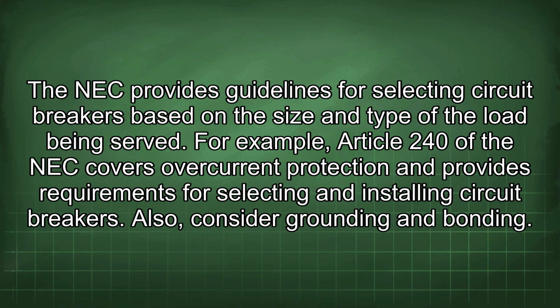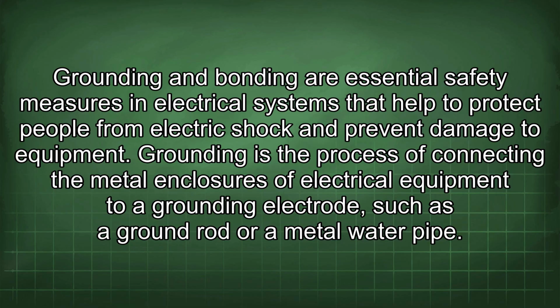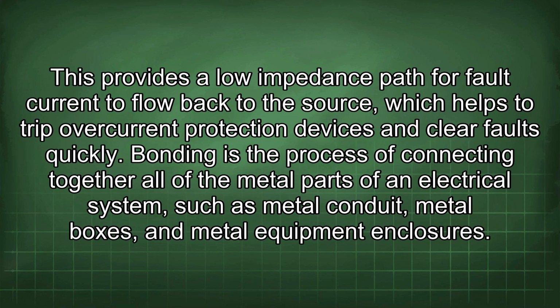Also, consider grounding and bonding. Grounding and bonding are essential safety measures in electrical systems that help to protect people from electric shock and prevent damage to equipment. Grounding is the process of connecting the metal enclosures of electrical equipment to a grounding electrode, such as a ground rod or a metal water pipe. This provides a low impedance path for fault current to flow back to the source, which helps to trip overcurrent protection devices and clear faults quickly. Bonding is the process of connecting together all of the metal parts of an electrical system, such as metal conduit, metal boxes, and metal equipment enclosures.